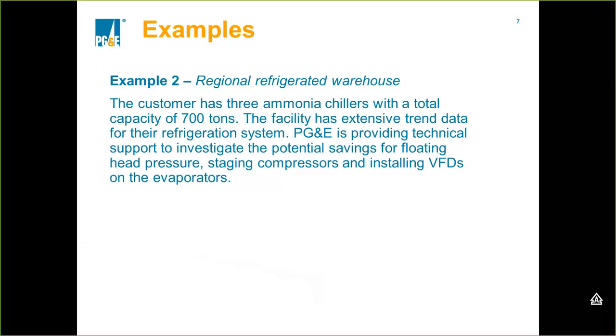Hello and thanks for joining us for example two of the refrigeration standard tool calculator. This is a more complicated example than example one — this is for a regional refrigerated warehouse. The customer has three ammonia chillers with a total capacity of 700 tons. Through an energy audit done by a PG&E engineer, three measures were identified: floating head pressure, restaging the compressors, and installing VFDs on the evaporator fans.